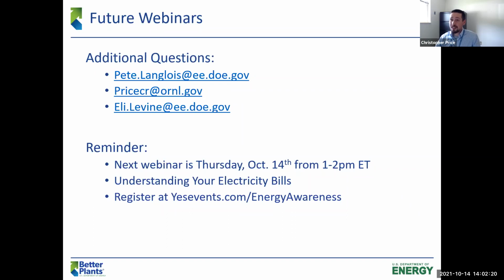Yes, you can overcorrect. You can have more capacitance in your facility than you have inductance, which would essentially lower your power factor again, just in the opposite direction. So you would get penalized for that. The issue is that having too much capacitance has other implications for the grid that can be worse than just having a low power factor.